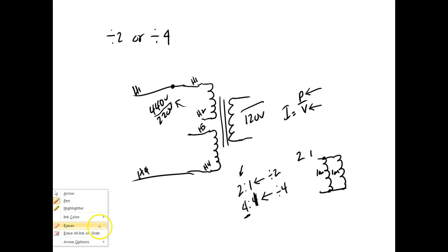So to wire it for low voltage, I put a jumper right here and a jumper right there, you understand that? If I want to wire it for high voltage, then I put a jumper in the middle. That means I never have crossing wires - the wires never cross. So I can look real fast and see if there are 2 jumpers up there. If they cross, it's wired wrong. If they don't cross, it might be wired for the wrong voltage, but it's easy to see. If I'm wired for low voltage, I'll have 2 jumpers. If I'm wired for high voltage, I'll have 1. So you can tell right off the bat whether the transformer is wired right or wrong.